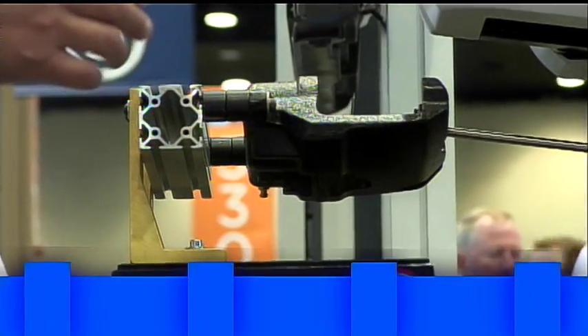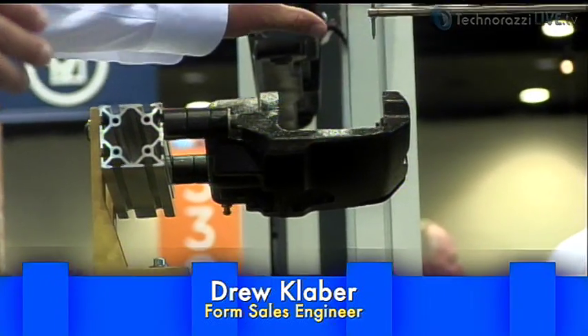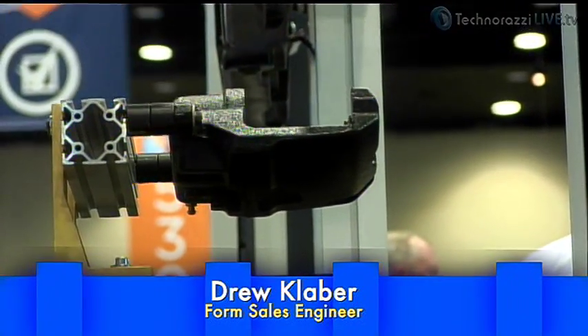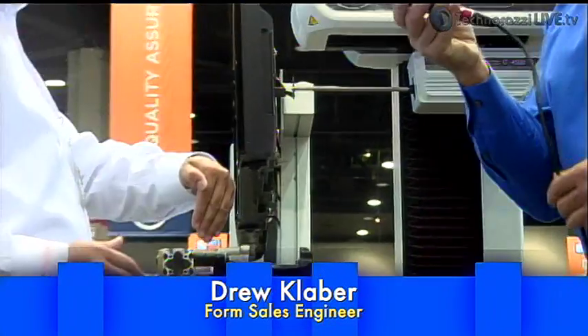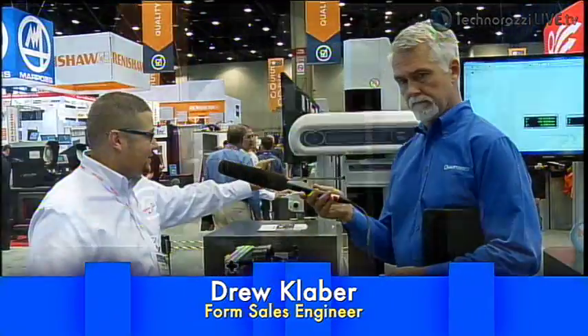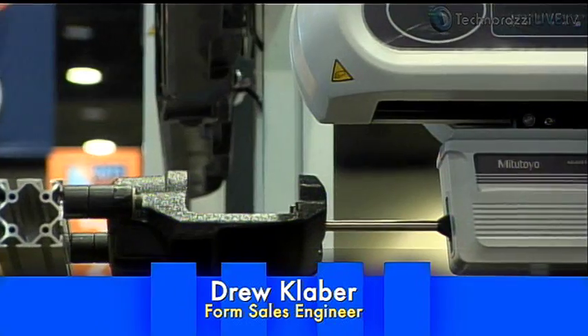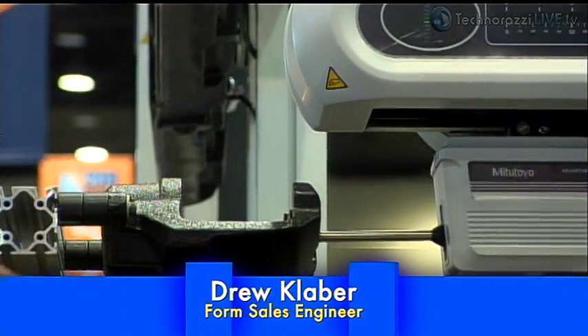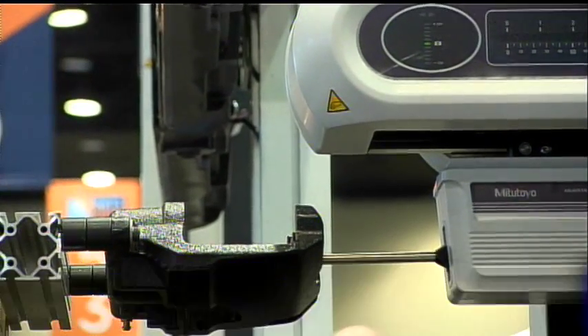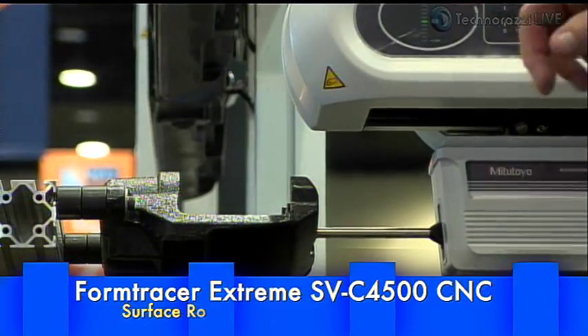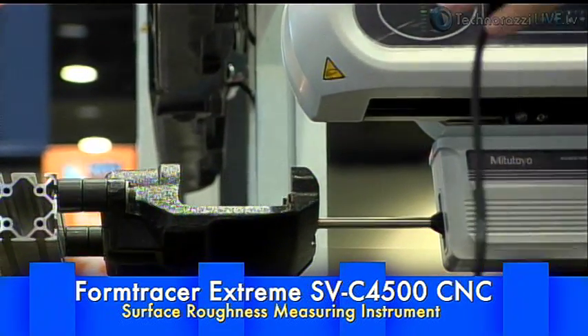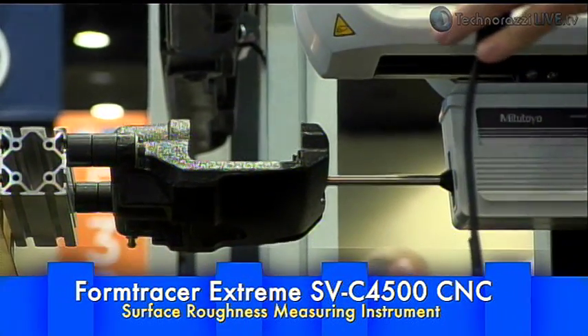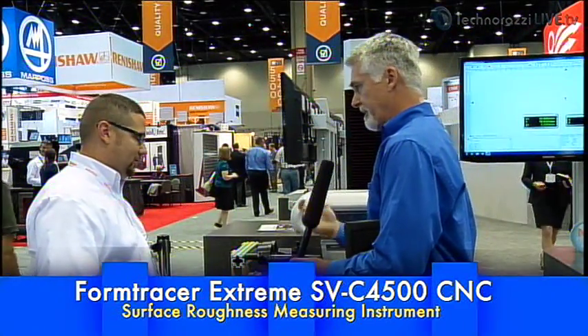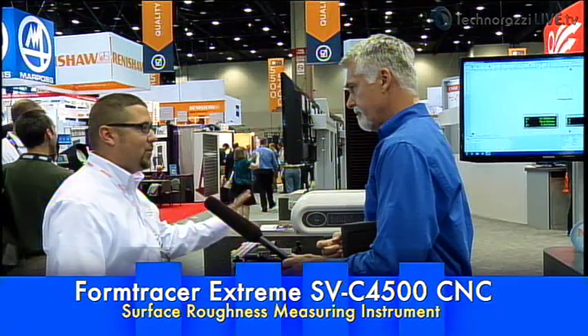And also, one thing that's unique about this is, if you take a look, we have the dual-sided stylus on here. The machine that you were just looking at with Len had a stylus in the 6 o'clock orientation. Well, now I have a stylus on the top and bottom, and I can do relative measurements between those. So I can do inside diameters, outside diameters, and get relative information between those. Oh, so if you had a single stylus, you'd have to rotate it over or something like that. Change the direction, recalibrate. This is already set up to go for that.